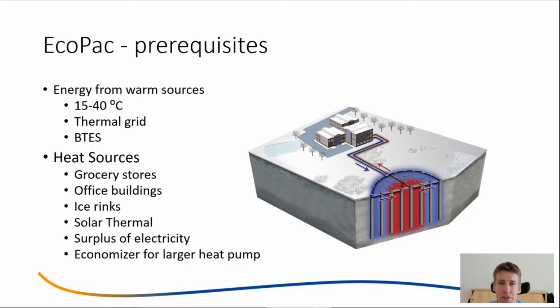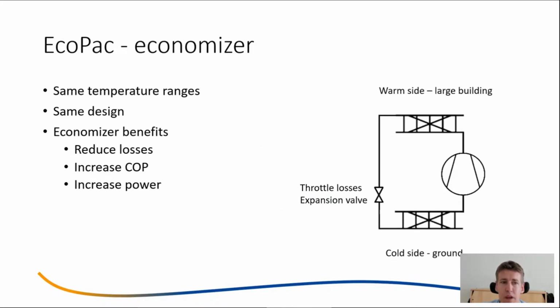A special application where EcoPac can also be used is as an economizer for a larger heat pump. And what is this then? For this application, we're talking about the same temperature ranges and the same design. The positive sides that we're aiming for are reduced losses, increased COP, and increased power. So what is an economizer?